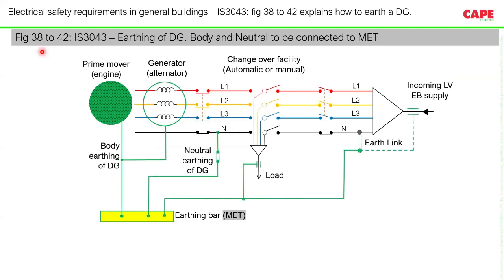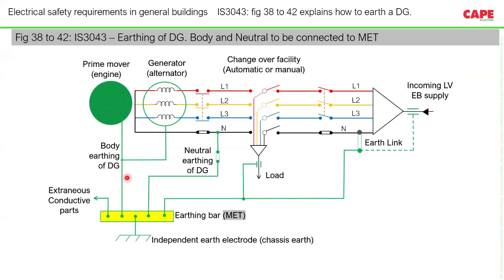This picture from IS 3043 is again just to show that earthing doesn't mean neutral two separate pits, bodies two separate pits for DG and the transformer. It is absolutely wrong. What you should do is protective equipotential bonding. The neutral of the transformer or DG has to be connected to an earthing bar. This picture is basically for a place where you have your own DG, body, alternator, and neutral connected to the common bus bar. And this is the correct way.